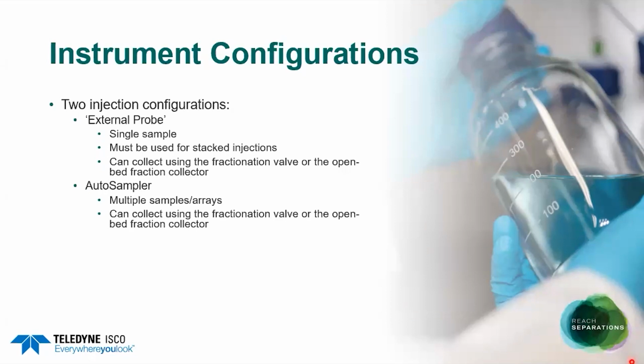We also have two injection possibilities on the SFC. Now, the first one is injecting through what's called the external probe, which draws your sample directly into the injection system, much the same way as other systems on the market. Now, we have the option to collect using the fractionation valve or the open bed fraction collector, but you have to bear in mind that this injection pathway is required if you're performing a stacked injection process and collecting into the open bed fraction collector. As you can imagine, the unit will get very confused when trying to inject and collect at the same time.